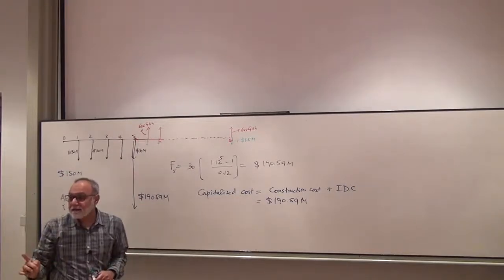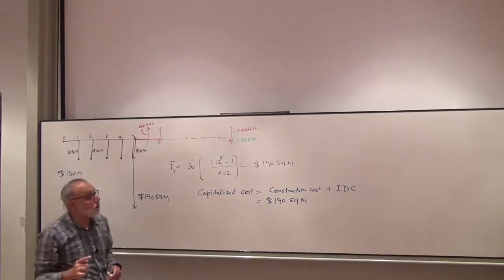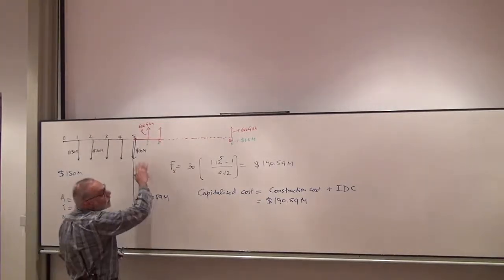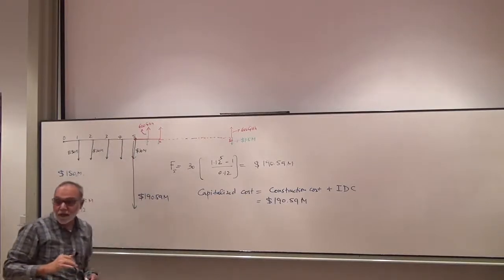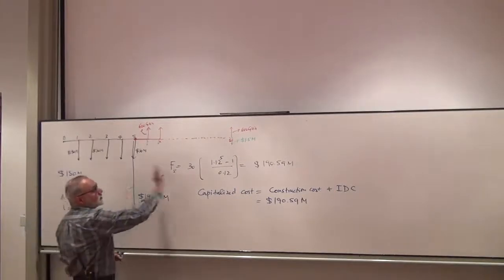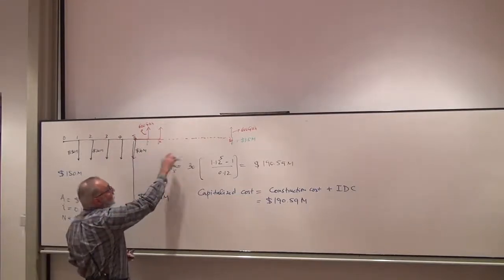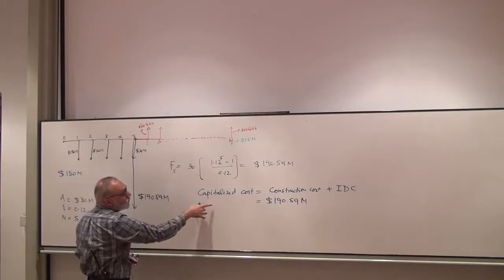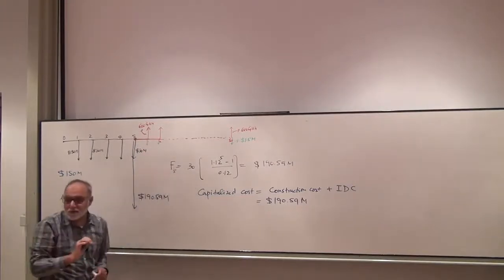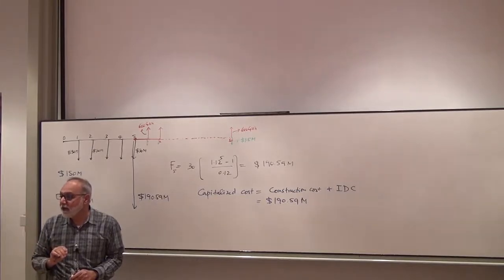Again, the energy will be discounted the same way, using the same present worth formula. And then total cost over total energy, or you will get the same answer. Or you spread this over 50 years and divide, and then you have annualized cost. So annual O&M cost plus annual capitalized cost will give total cost. We will have total cost divided by total annual energy, and that will give us our answer.